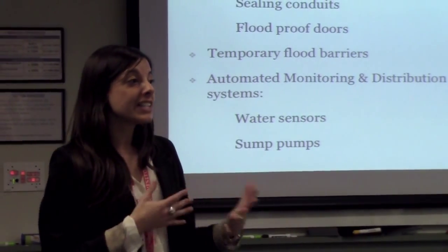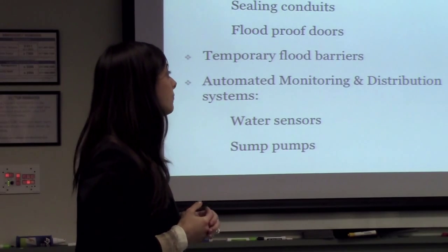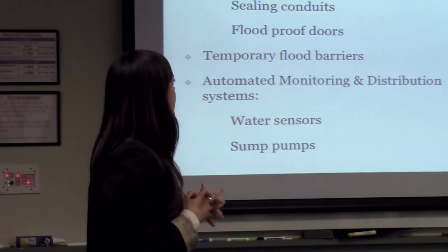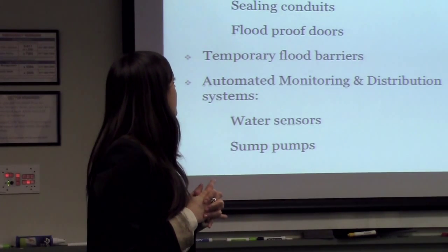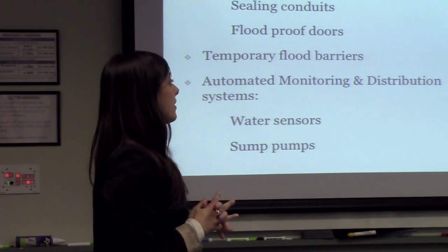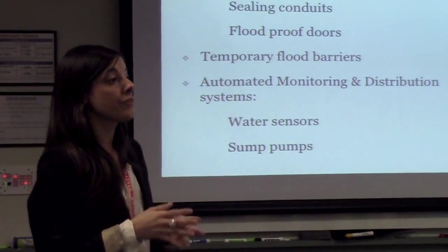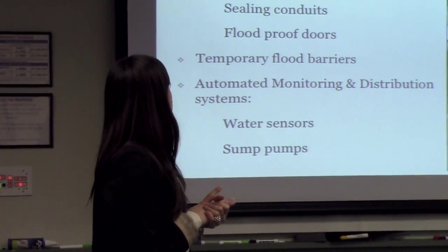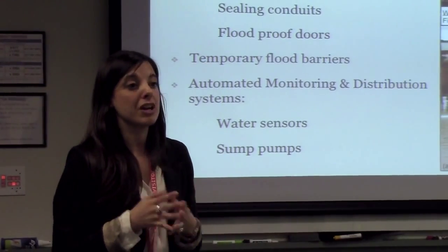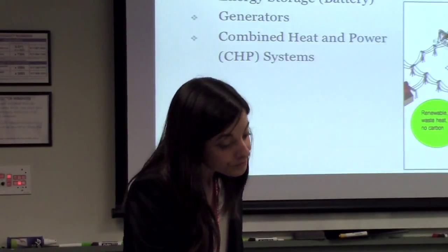They don't operate equally, and any disruption of their service will have consequences in the electric service of Logan. They are very vulnerable to flooding under a category 2 hurricane, so we need to weatherproof those substations and also provide flood barriers in order to prevent water from getting there.